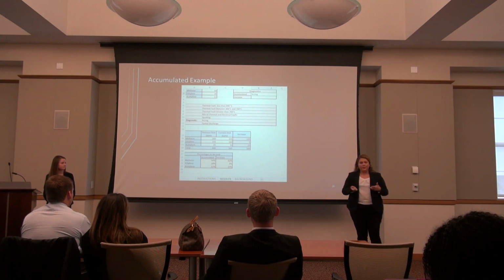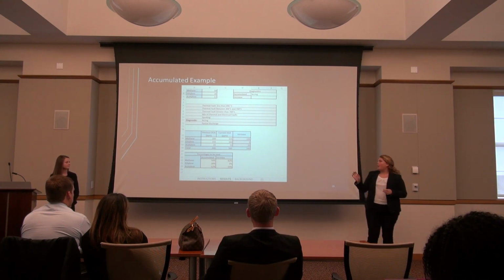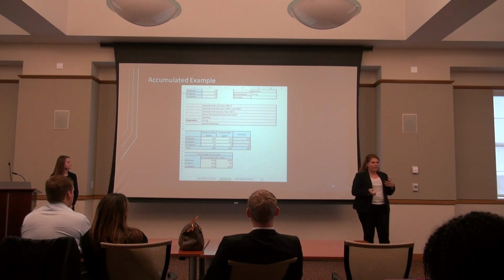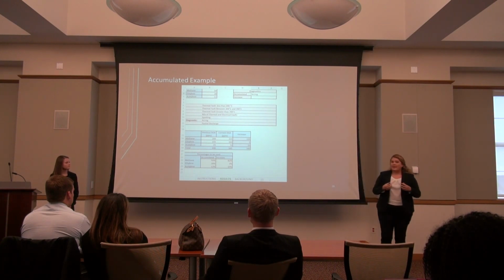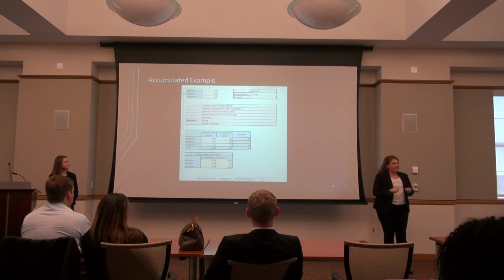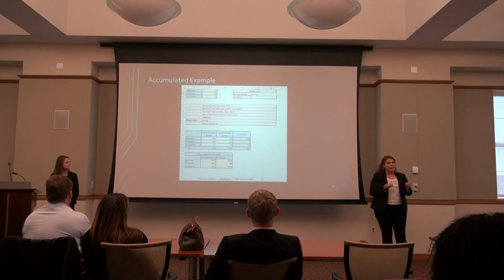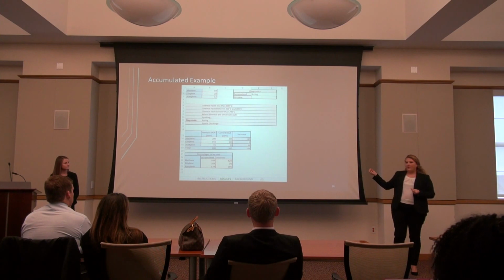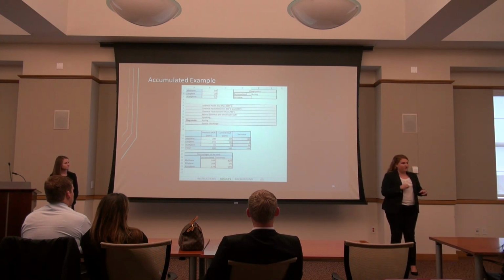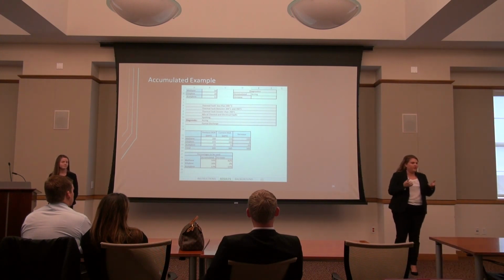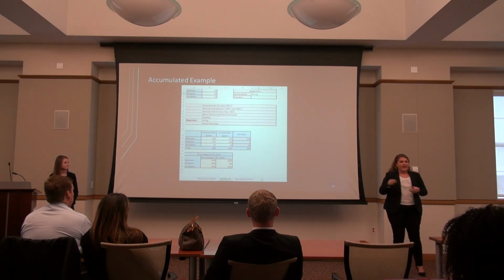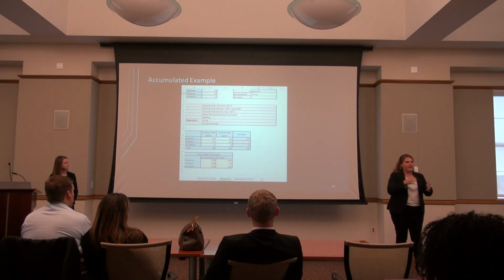For this test we did a lot of reading and searching. We found that using both the accumulated gas and the increased gas value, if the percentages and results both match, it's extremely likely that that problem is happening. So imagine if we have arcing corona, meaning there's some electrical discharge and thermal discharge that can probably cause a fire inside the transformer. If both indicate that, we know we have to shut it down or see if we can redirect the current to some other transformers.